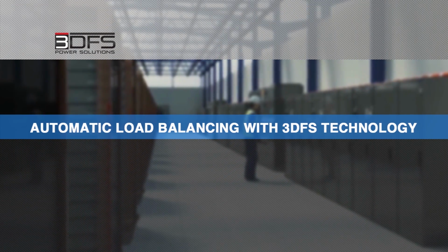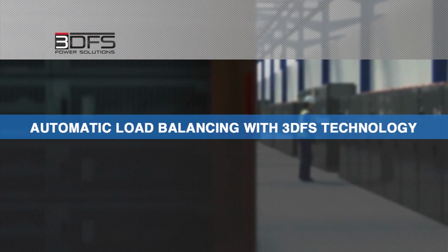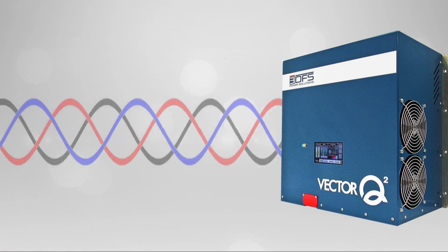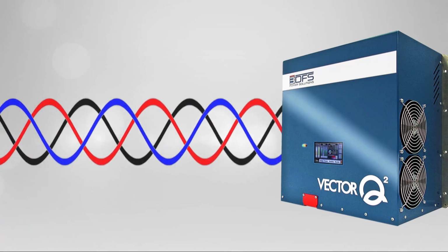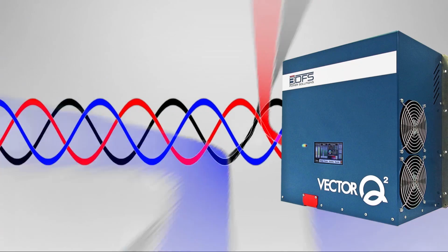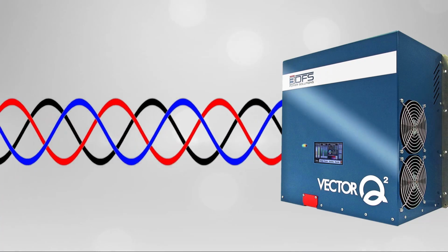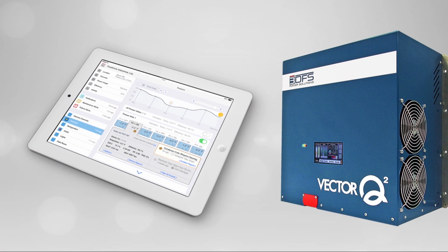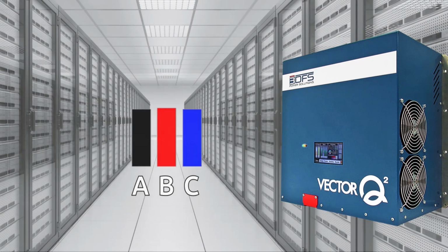Now we will show how 3DFS technology is the first commercially available product that automatically balances the loads across the phases, eliminating human error from this process. The power controller analyzes the real-time power demand and immediately optimizes electricity and reports data through our secure user interface. During this process, the load balance across the phases is also monitored and corrected, providing dynamic load balancing at all times. The automatic load balancing feature comes standard with the VectorQ2 unit.